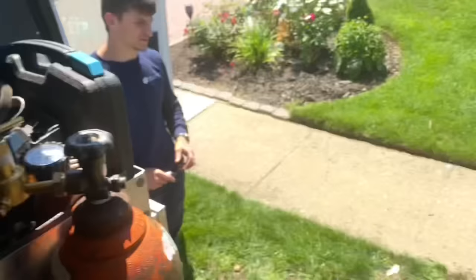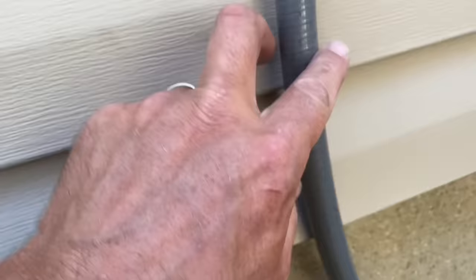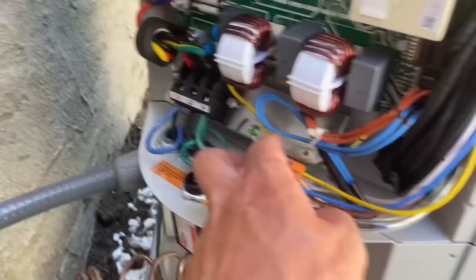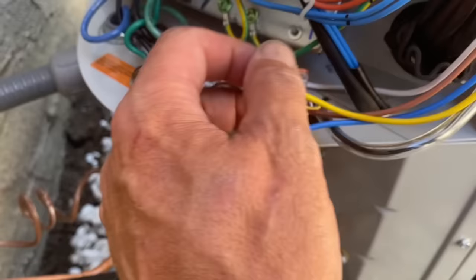All right, we are done with low voltage wiring. There's our disconnect. It's off. We're going to throw in a little strap right here because it's code. Not here, though. South Carolina, it's code. Put a strap right there. Here's our Rectorseal RSH50 surge protector, which gets wired to L1, L2, the same way you have power. Here is our low voltage wiring, the blue is our O and B wire, the reversing valve. The yellow wire is to turn on the contactor, which is one of these things.